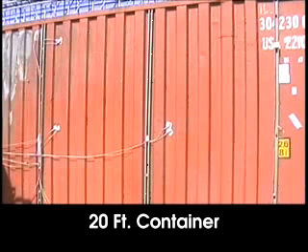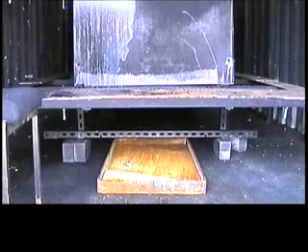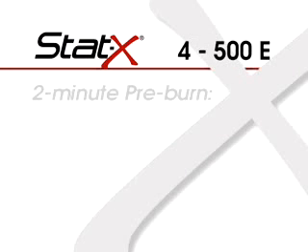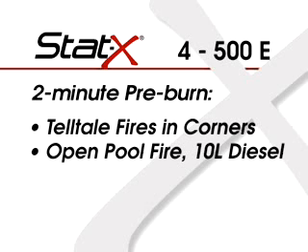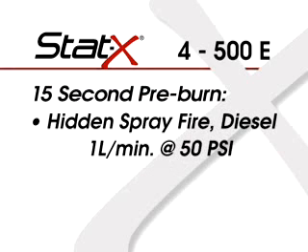The tests were conducted in a standard UN 20-foot shipping container to simulate a typical small marine machinery space. Design concentration was 58 grams per cubic meter. The test combined four separate fires: telltale cup fires in the corners, an open pool fire containing 10 liters of diesel, a hidden pool fire under a simulated marine engine containing 5 liters each of diesel fuel and lube oil, and a hidden spray fire of diesel fuel discharged at 1 liter per minute at approximately 50 psi.